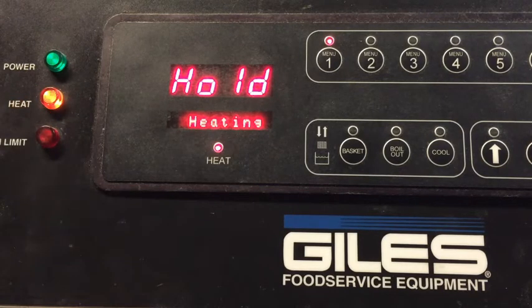it will stay off. In most cases, what you're going to find is that the probe is actually, if it's doing it, say at 200 and some degrees or something like that, as opposed to the 450 degrees that it's set for, what you're going to find is that the tip of that element or probe, the tip of the probe is too close to the heat element. So then you're going to want to go ahead and make the adjustment that I'm going to show you in the next slide.